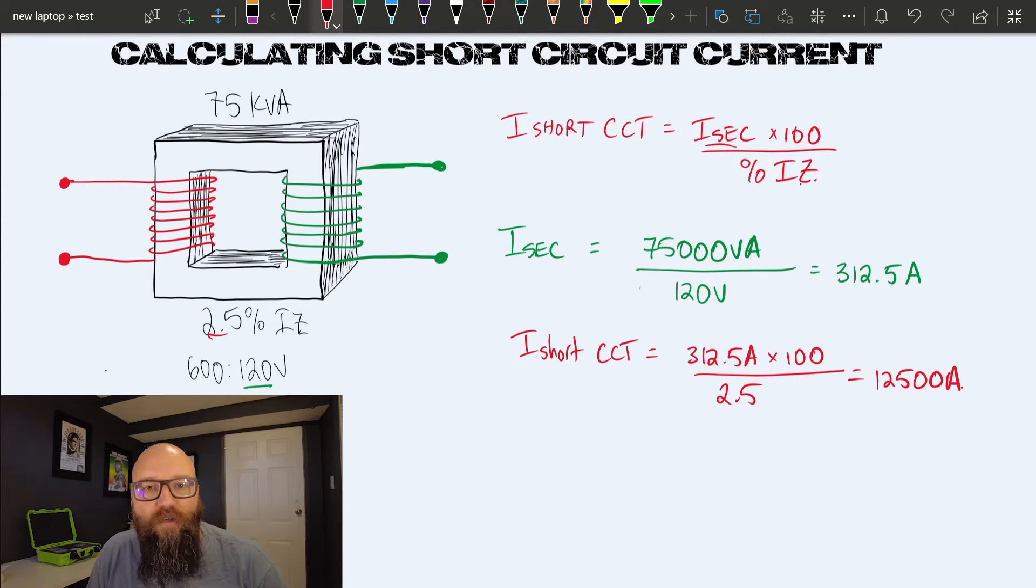Why is that number important? If I'm selecting overcurrent devices, one thing I need to be cognizant of is what is the interrupting rating of my device? Can my device handle that 12,500 amps? A standard interrupting rating on an overcurrent device is generally 10,000 amps if not marked. That would not sufficiently protect us in a short circuit. I would have to go with something at least equal to my short circuit current or higher. I can always be higher with interrupting rating. My short circuit current can never be higher than my interrupting rating.